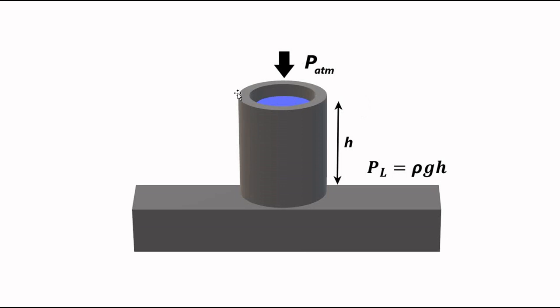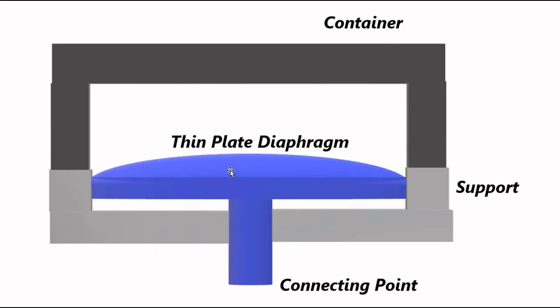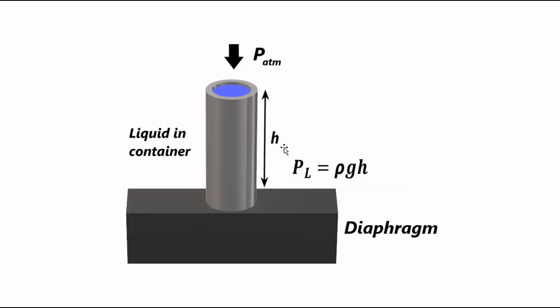Again, there are two conditions here. If the lid is closed, only the liquid level pressure will be measured by the sensor. If it is exposed, atmospheric pressure will come into play, and the total pressure, P atmosphere plus the liquid level pressure, is measured by the sensing element. So here the sensor is this diaphragm, which is present in this kind of arrangement, where we have an encapsulation chamber, then this thin plate diaphragm connected to two flanges, two fixed points, the supports, and then a tubular arrangement connected to the source of pressure, the connecting tube.